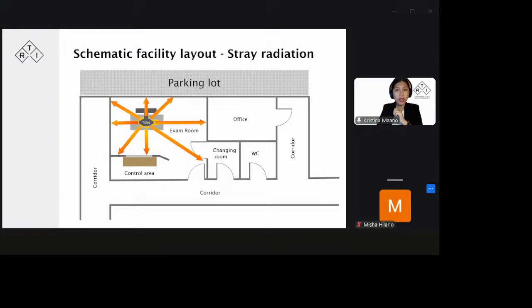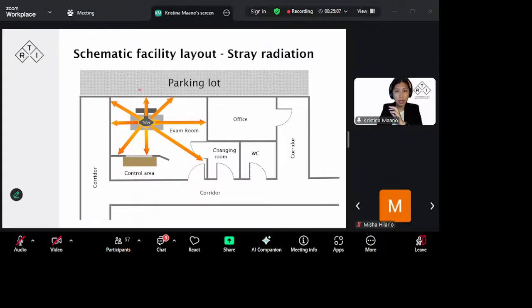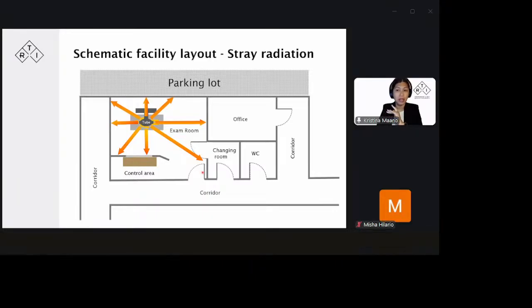So this, of course, can be a concern from a radiation safety point of view, since this may impact adjacent areas around the X-ray room. And both the fluence and the quality of this stray radiation have an angular dependence, and it also does not have the same intensity in all directions. So it's a very special concern, especially in fluoroscopy procedures, which are longer.